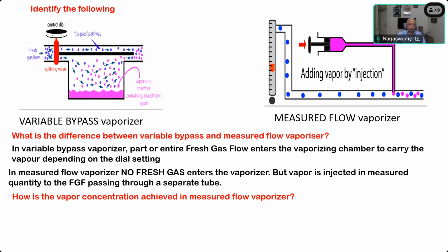For example, in desflurane, you can give up to a maximum of what percentage? 18%. 18% you can give. How is it? You can give 1%, you can give 2%, you can give 12%, you can give 18%. How is it possible when the gases are not directly going into the vaporizing chamber? By manipulating the fresh gas flows. Pressure transducer. There are two things, resistors and pressure transducers.